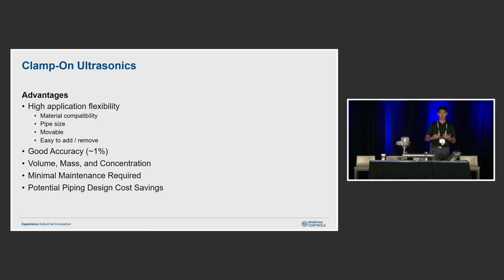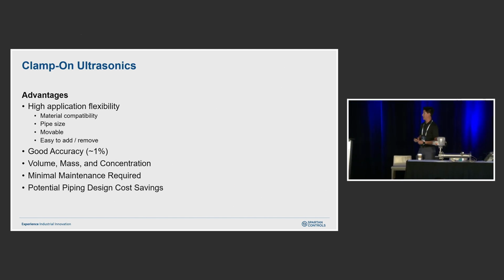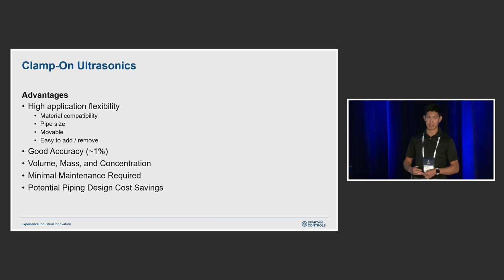A lot of those things we can really accommodate and accomplish because we don't need to have any pipe changes, right? So that's another big advantage. So if you, say, want to add a flow measurement to a location that previously didn't have it, if you want to add something like a magnetic flow meter, you would have to cut the pipe, make some pipe changes, add the mag in, and we don't really have those limitations with clamp-on ultrasonic.